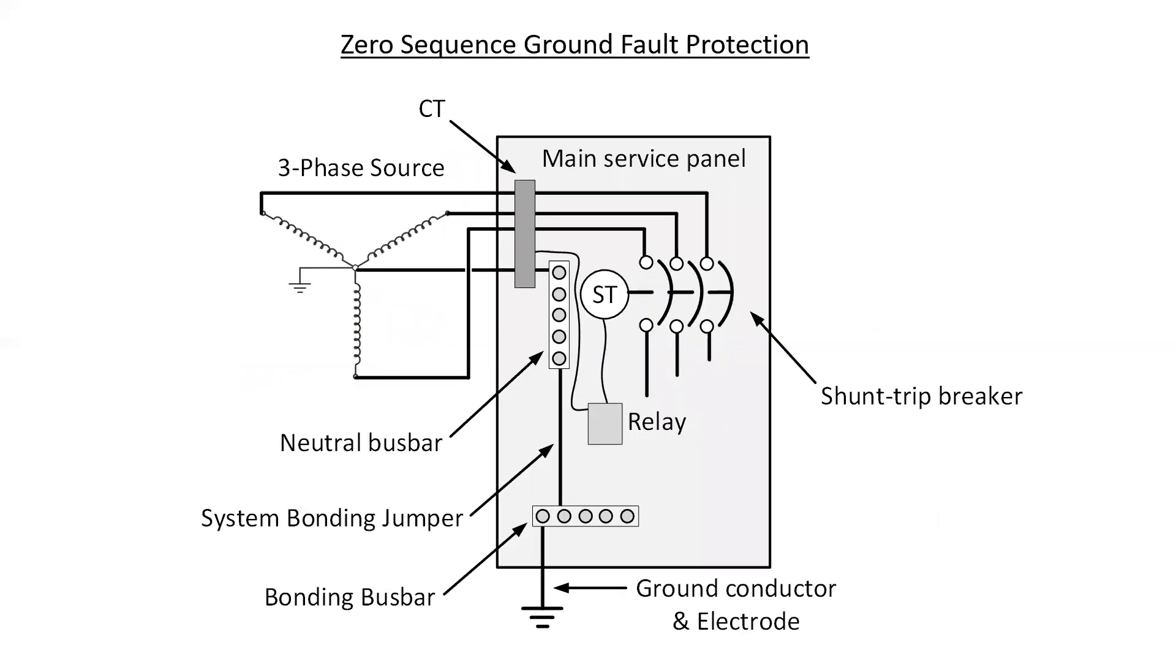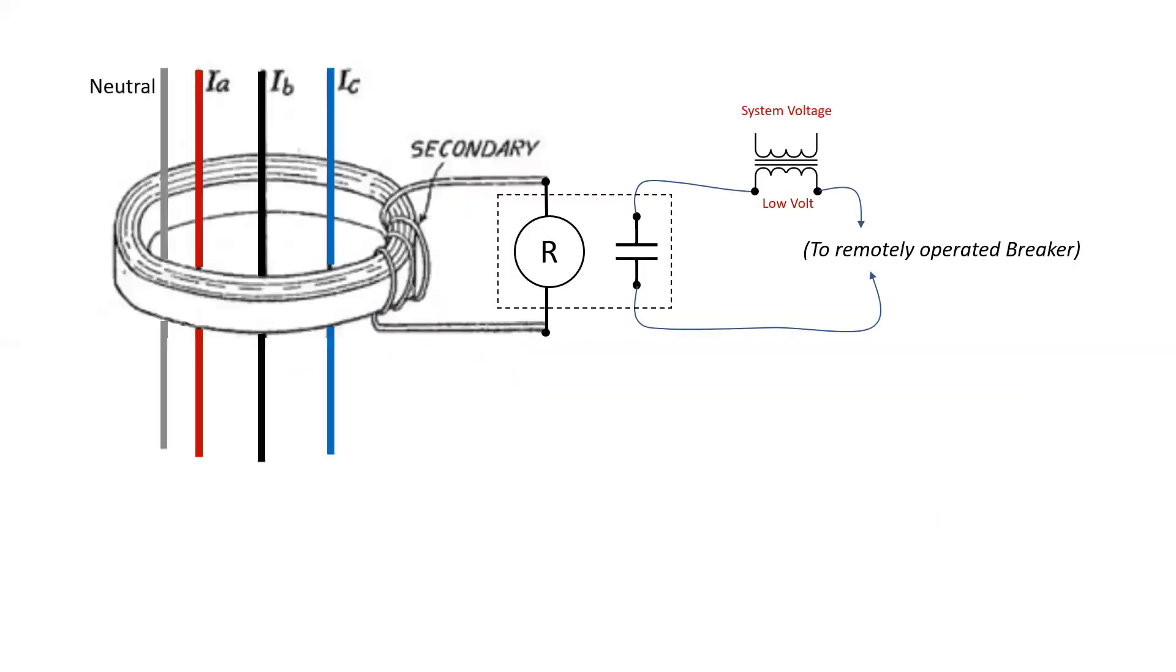A zero sequence is much the same, and it's simply a larger CT that has all of the circuit conductors inside it. Same idea where there's a relay and a shunt trip unit. In this situation, what we're looking for is an unequal value of current.